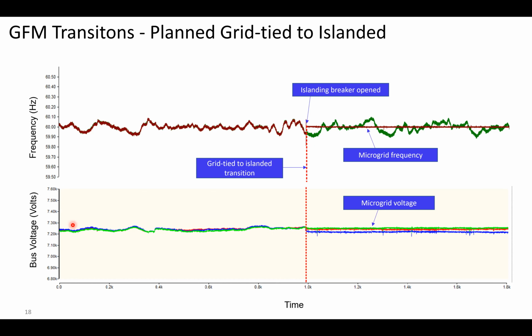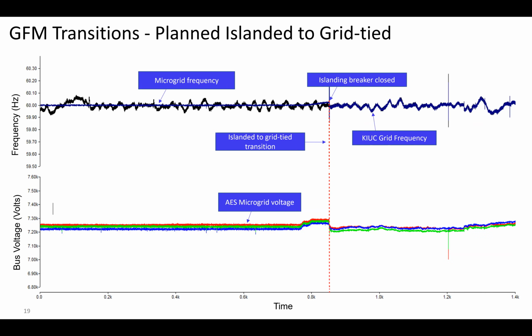The same thing here with voltage. So the voltage at the bus is recorded at disconnect, and that's the microgrid voltage while disconnected from the grid. So that's a planned grid tied to islanded sequence. In theory, it's probably an easier sequence to go through versus something that happens unexpectedly. The next transition is planned islanded back to grid tied.